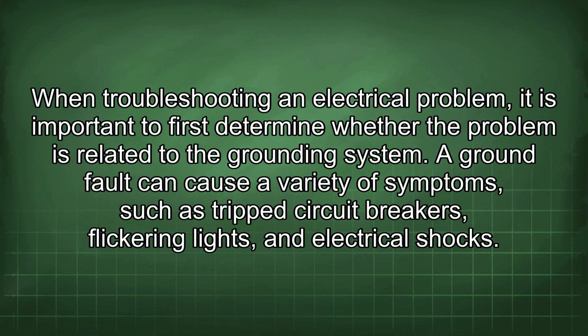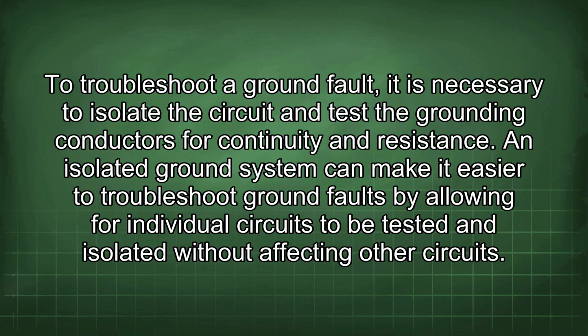system. When troubleshooting an electrical problem, it is important to first determine whether the problem is related to the grounding system. A ground fault can cause a variety of symptoms such as tripped circuit breakers, flickering lights, and electrical shocks. To troubleshoot a ground fault, it is necessary to isolate the circuit and test the grounding conductors for continuity and resistance. An isolated ground system can make it easier to troubleshoot ground faults by allowing for individual circuits to be tested and isolated without affecting other circuits.